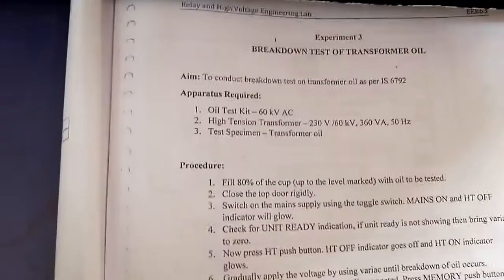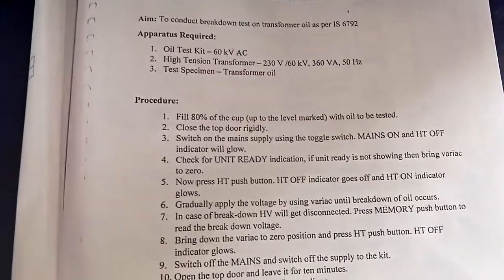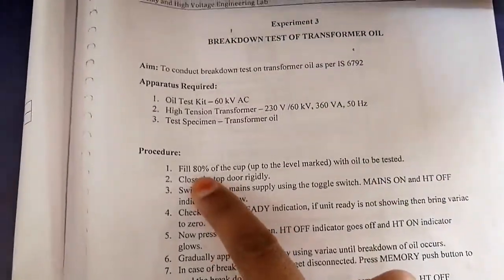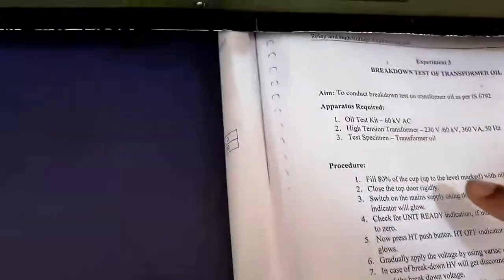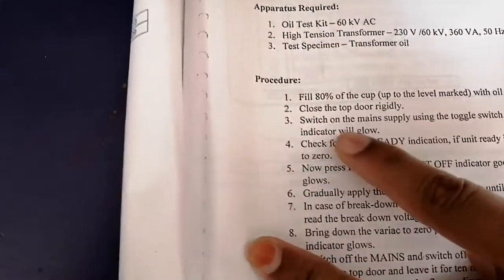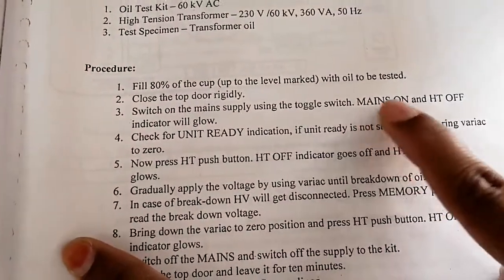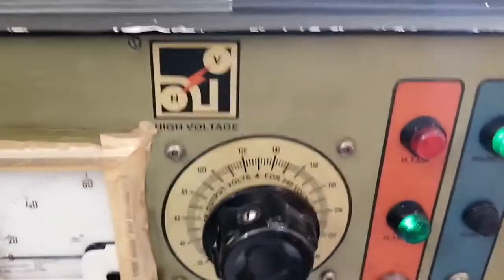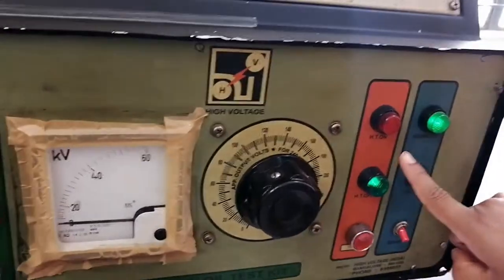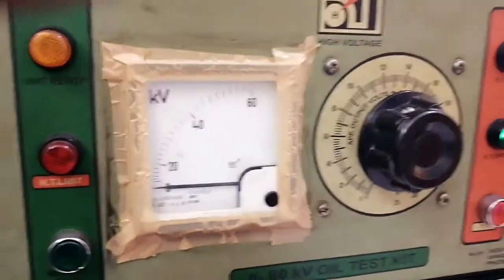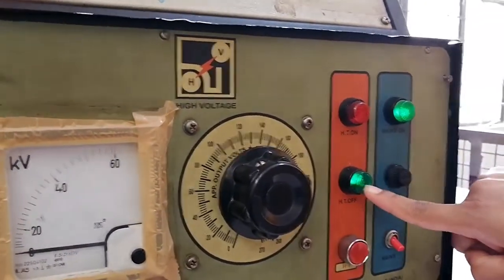So what is the procedure? The first thing you should confirm is that the transformer tank is filled 80% with the oil to be tested, as we showed previously. Next, close the door of the transformer oil tank, then switch on the main supply using the toggle switch. Mains on, and the HT off indicator will glow. Once you close the transformer oil tank, you have to turn on here and here. HT should be off, but mains should be on. This indicator says the main switch is on and HT is off.